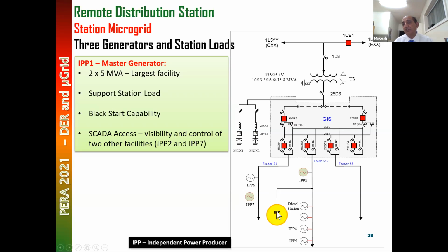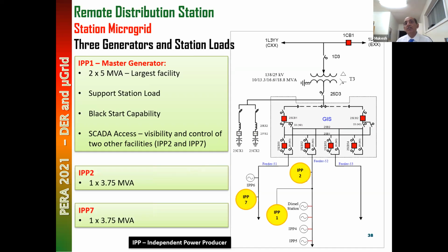So this is the master station for three reasons: it is large, and it has a partnership with these two plants. There is one common control center among the three, but our own control center has no ability to control all three. If we had the ability to control all three generators, then we could have done a plant transition. We don't have the infrastructure or SCADA system to operate and control these three IPPs from our control desk. That is a BC Hydro control desk. The other two generators are small, 3.7 MVA.